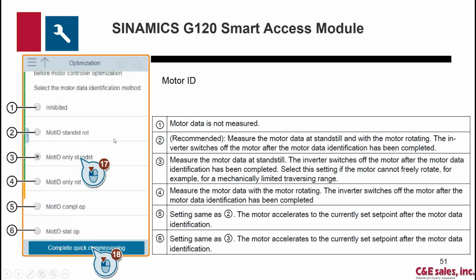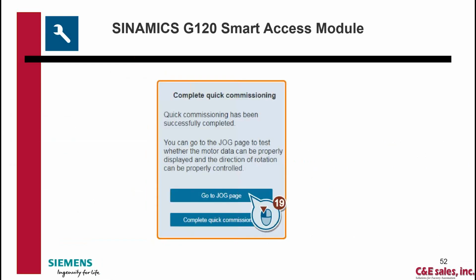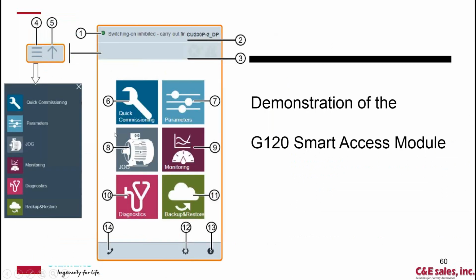So these are the drive's going to basically ping the motor or apply voltage to the motor and make some resistance type measurements and set some parameters accordingly. So typically in the G120 we'd recommend at least some type of motor ID. Typically I'm going to do only at standstill, and that's what I'll show you in the example. Then we'll complete the quick commissioning wizard. You can go to the jog page here or complete, either one. Again, here's the menu, what it's going to look like in the web page, and I'll start the demonstration there.